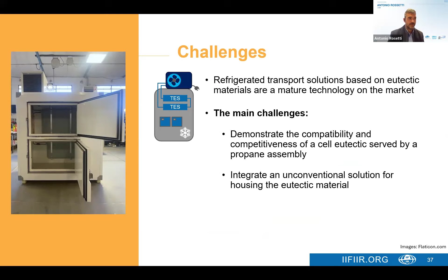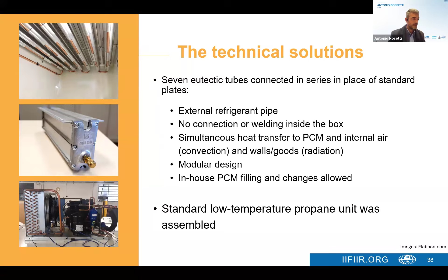This has many advantages. One is that the refrigerant tube is external, so it can more easily comply with safety standards when you have a flammable refrigerant, because you can inspect it and there's no connection or welding inside the box. It can also exchange heat by convection and radiation with the walls and the goods inside the box, which, if used as temporary storage, can be a positive effect. Regarding the propane unit, it was a quite standard unit, nothing very interesting there.